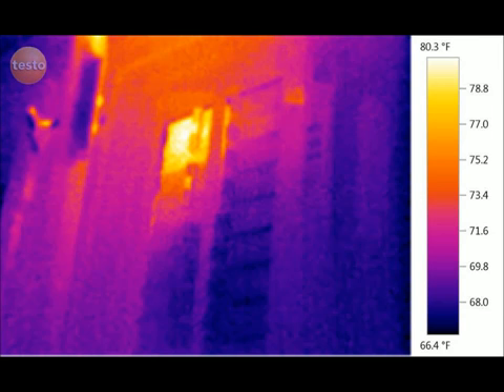In this thermogram, we see an electrical disconnect switch, more commonly referred to as a breaker. This image was taken during a routine inspection of a commercial restaurant facility. The bright coloration alerted the thermographer that there may be a potential problem. Upon further examination, after removing the panel cover and attaching electrical testing equipment to the circuit, it was determined that there was not a problem. Had this breaker switch failed, it would have cost the restaurant hundreds of dollars in lost revenue for the night. This breaker controlled the refrigeration unit where large quantities of meat were stored for that week's menu.